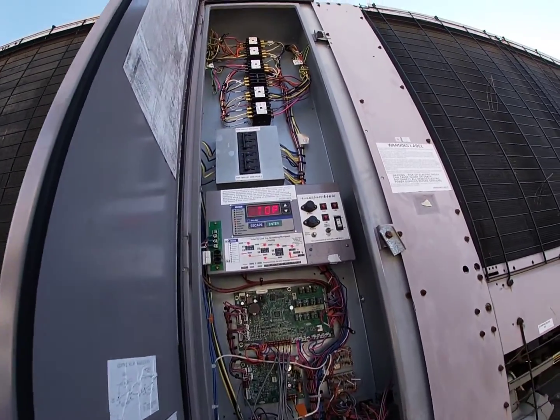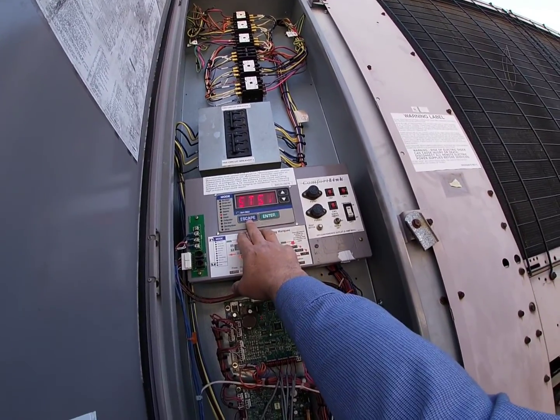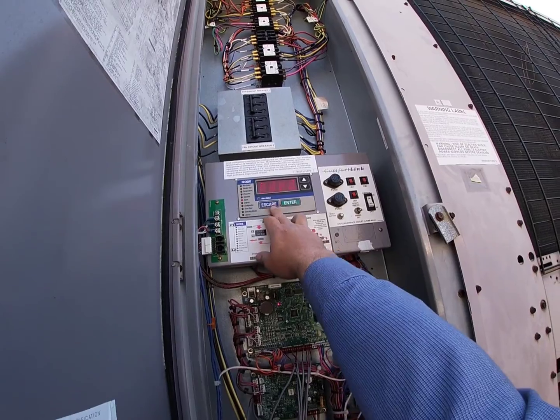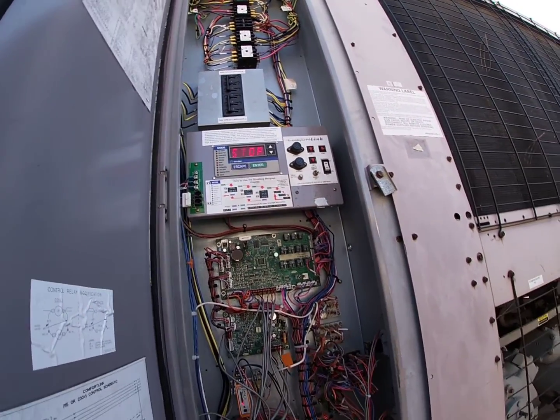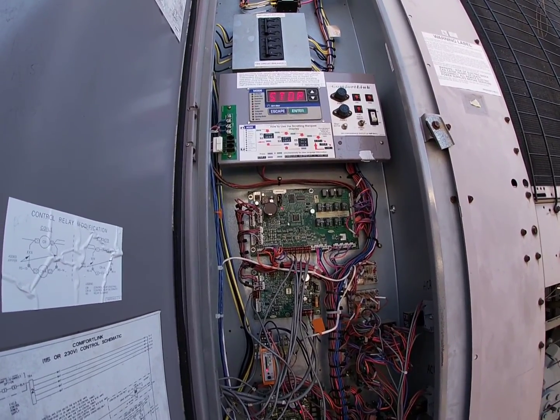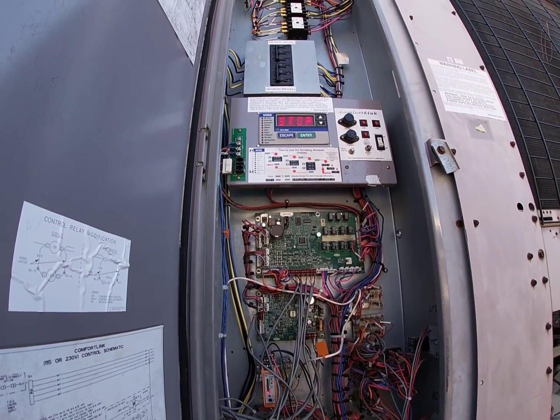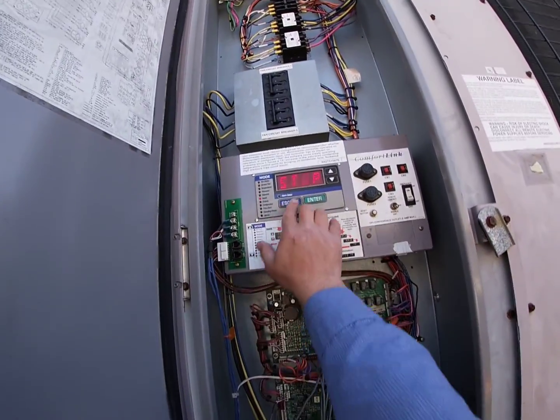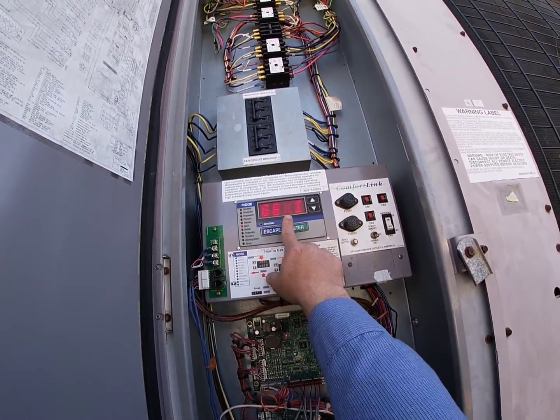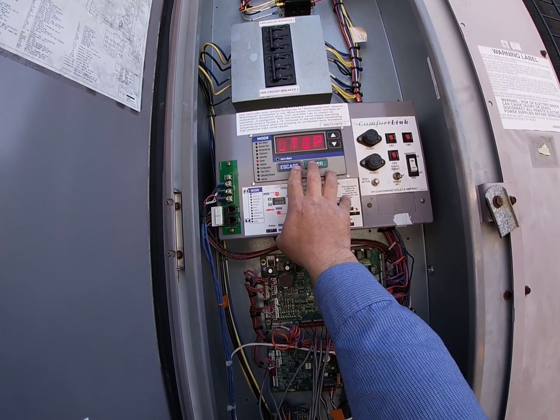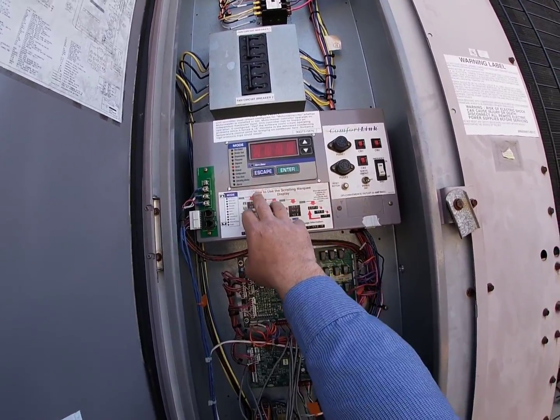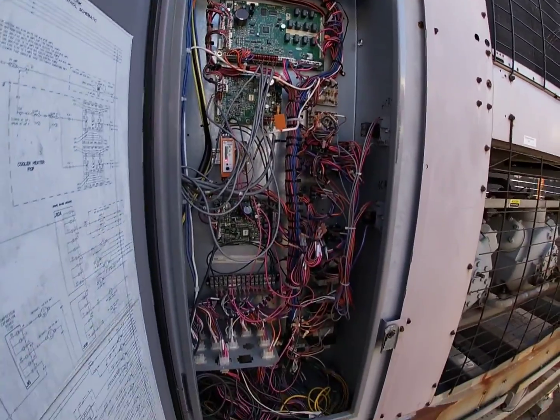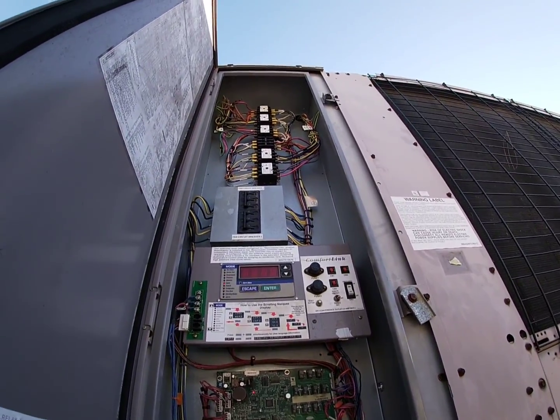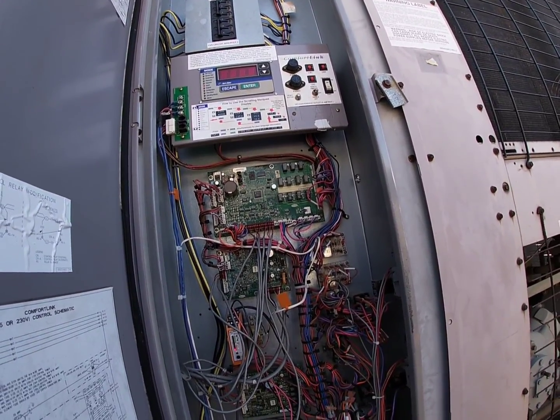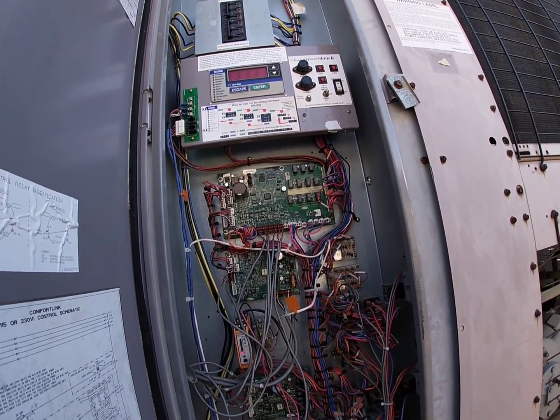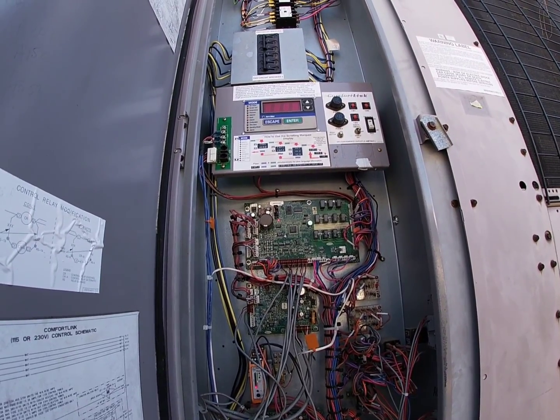All right, guys, well, as you can see, it's still in the stop signal. They want me to go ahead and replace that condenser fan motor, and then we'll run it. Right now their BAS has it locked out on outside temperature since it's below 60 degrees outside and won't let the chiller run. But so anyways, to get to that point, you can go here to your inputs, Gen I, start stop, and it's showing stop right now. So we don't have any signal yet for their chiller to come on. So anyhow, we'll get that condenser fan motor changed out, and then I'll film a little bit more when those compressors can come on, make sure everything's okay with those. So we'll start there. All right, guys, I'll get with y'all.